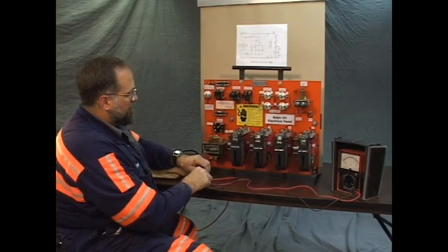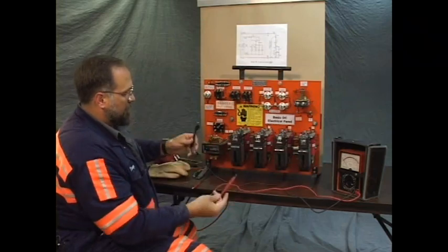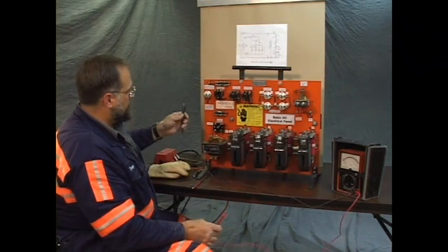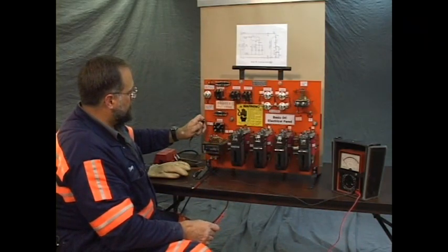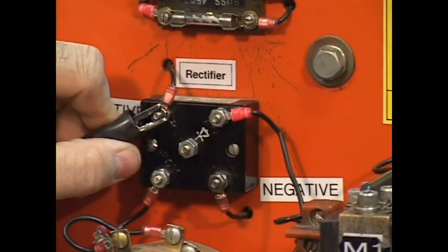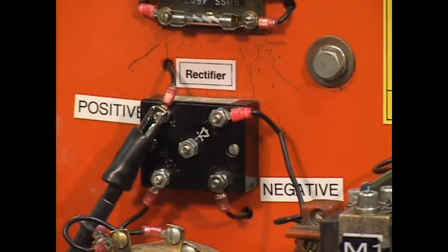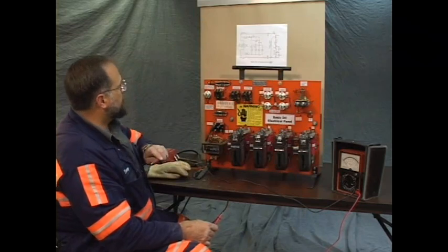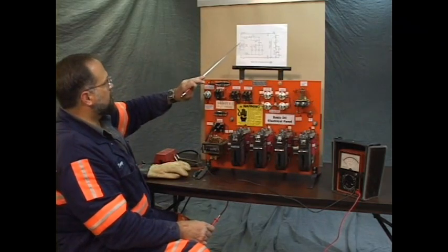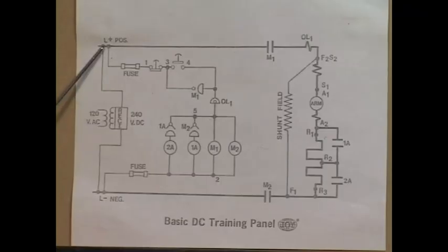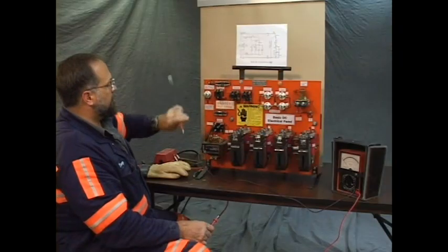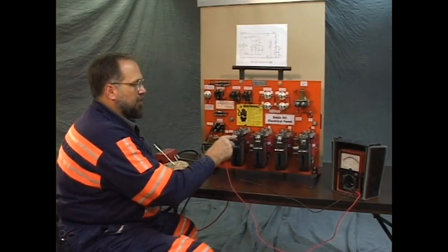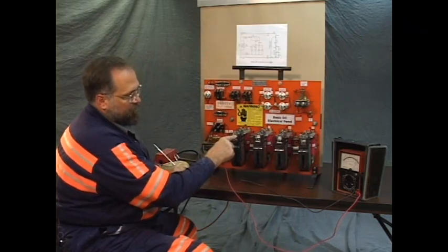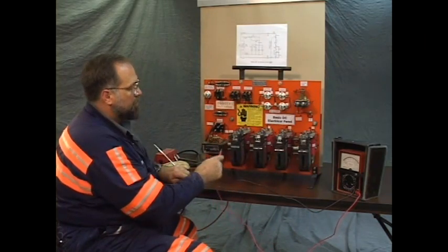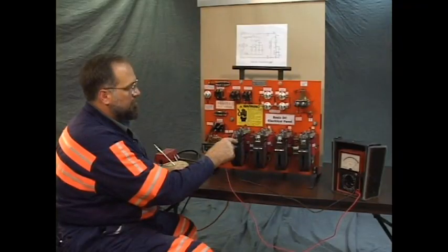I'm going to attach my black meter lead with alligator clip to the positive terminal of the rectifier. And the first place to test, the first wire, would be the top front of the M1 starter. And if you'll refer to the meter, you'll see that we have a circuit. We have continuity on that wire.